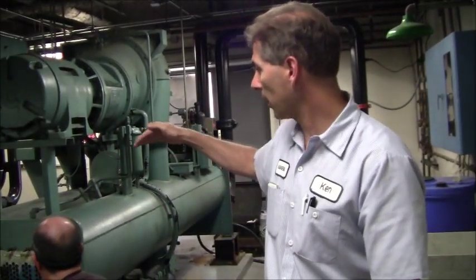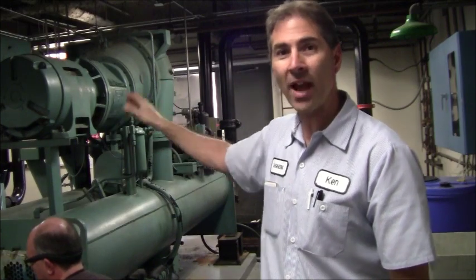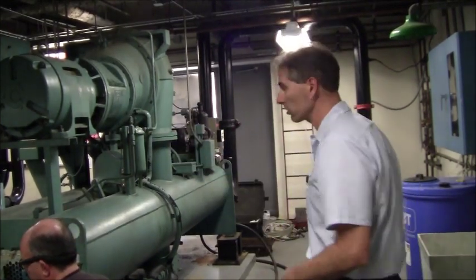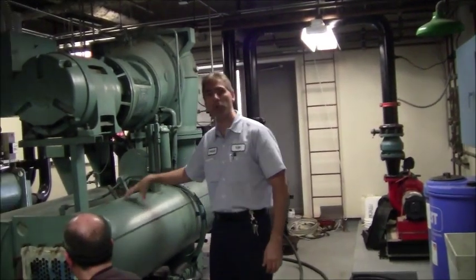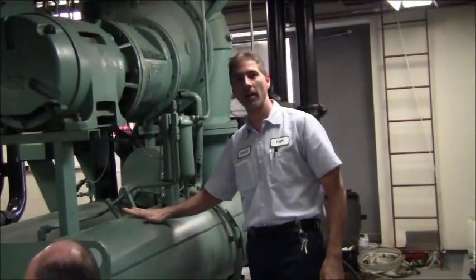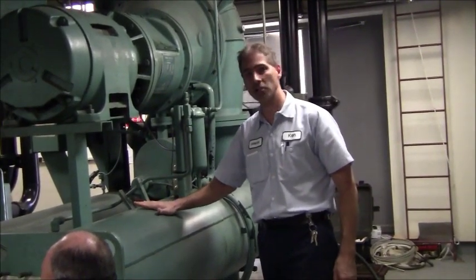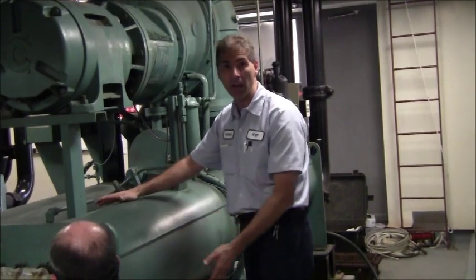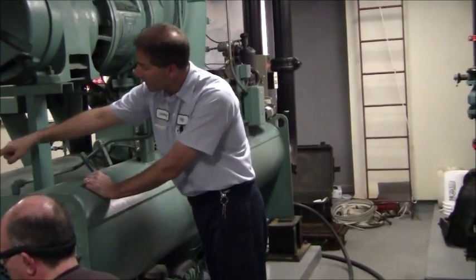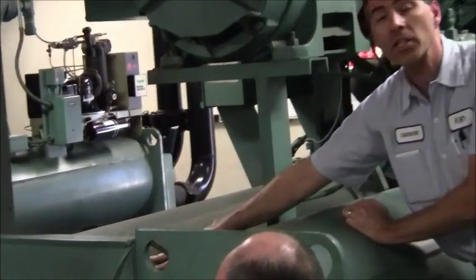Today's training, what we're doing is we are eddy-current testing the tubes that are in this chiller right behind me. There's a condensing section and evaporator section. So let me go over the chiller itself. It's a shell and tube chiller. This here that I've got my hand on, this is the condenser. There's no insulation around this shell. The evaporator, which is right over here, has insulation on it, keeping your water chilled.